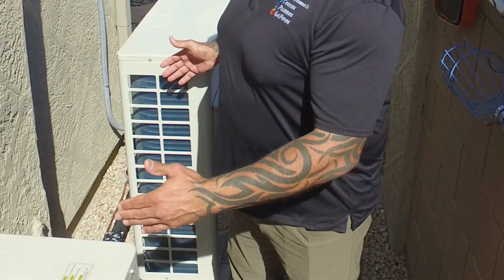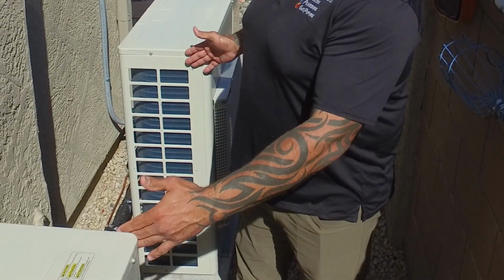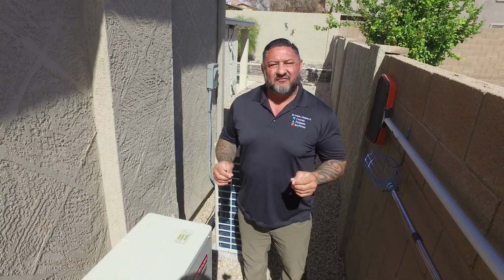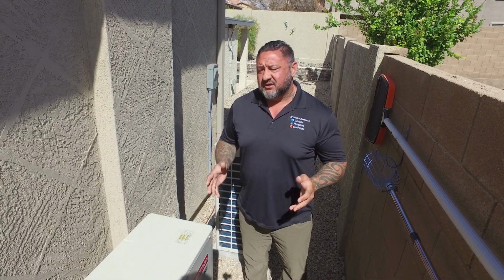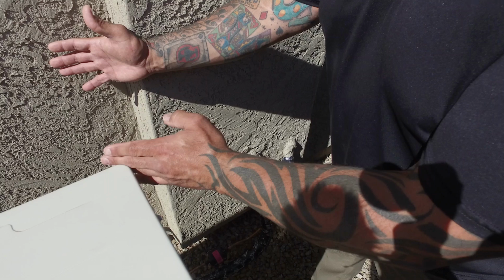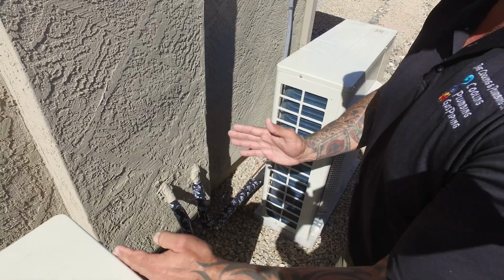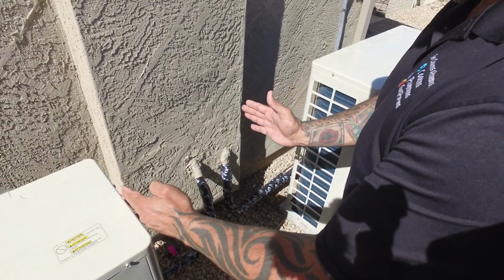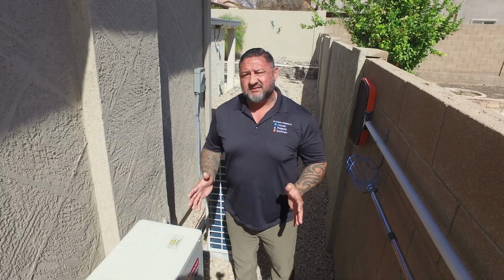So typically in a cube style system, we need to be a minimum of 12 inches off of any solid surface, and we need to be 2 feet, 24 inches, away from another air conditioning system. In inverter technology, those rules have changed. And we can be somewhere between 3 and 6 inches off the wall, and we can be within 1 foot of each other. However, this is not a clean room.